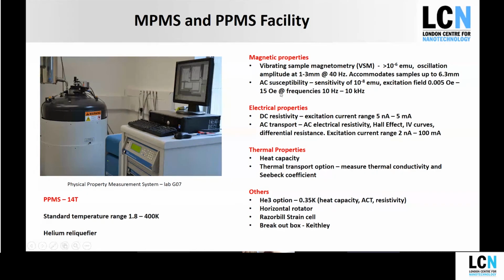We have AC susceptibility, with a range of sensitivities, fields and frequencies you can do. For electrical properties, we can measure DC resistivity, AC transport, so resistivity, Hall effect, IV curves, differential resistance. For thermal properties, heat capacity and the TTO option. And then there's various other options. Helium-3 will extend the temperature range down to 0.35 Kelvin, and you can use that with heat capacity, ACT, and resistivity. There's a horizontal rotator, a strain gauge, and you can also equip it with a home-built breakout box so you can interface with the instrument.